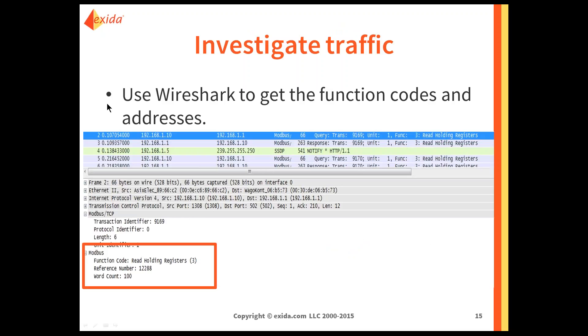In this case we've used Wireshark. Wireshark is your friend when you're investigating this traffic. Wireshark understands Modbus TCP — it knows what to do with it when it sees it on the network. We're using Wireshark to monitor the traffic between two devices. Looking at the very first line, we're talking from address .10 to the device at address .1. Opening the packet detail, Wireshark tells me it's a Modbus command — function code read-holding registers, function code 3, reference number (starting address) of 12288, and it's telling me I want to read 100 registers. It just told me everything I needed about this command to begin programming my DPI device.